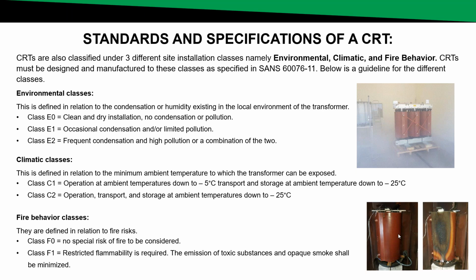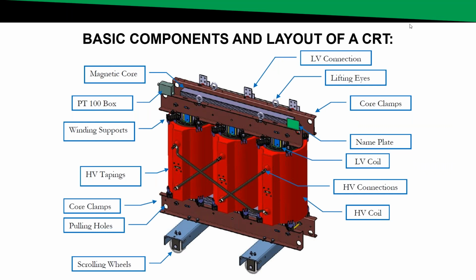Now that we've had a look at the basic standards and specifications required for cast resin transformers, let's have a look at the basic layout of a cast resin transformer. So cast resin transformers' layout and basic components are very similar to that of the oil-filled transformers. You've got a magnetic core, you've got HV windings with the relevant HV winding connections. You've got an LV winding with the relevant LV winding connections. You've got your winding supporting blocks.